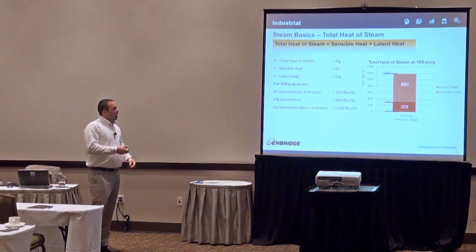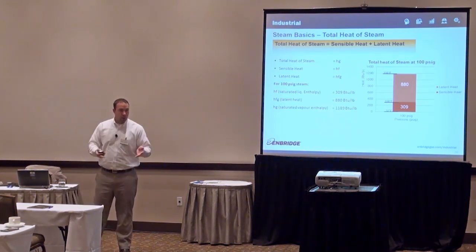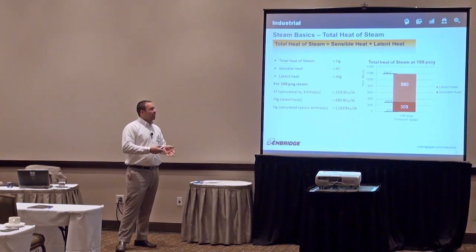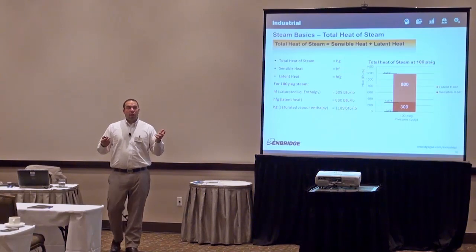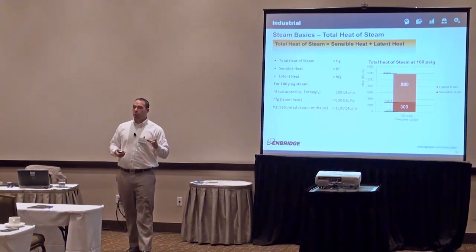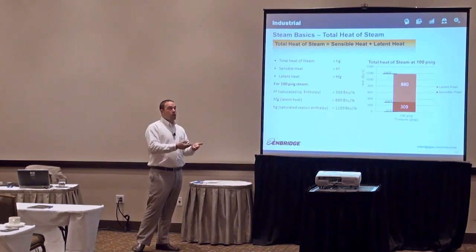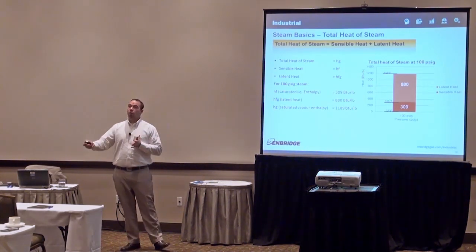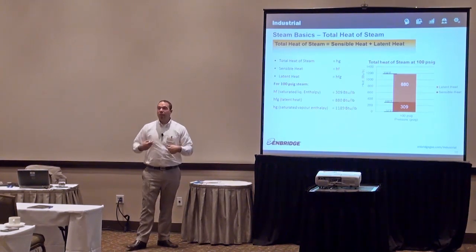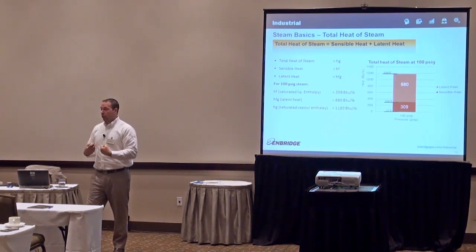So HF is how much energy we have in the liquid. So the saturated liquid relative to 0 degrees C or 32 degrees F, how much energy do we have in the water? HFG is how much energy does it actually take to do the phase change? How many BTUs per pound did we have to put in to get the liquid to go to a gas? And most importantly, when we condense it in our end user, that's how much energy we're going to get back, or we're going to get out of it.